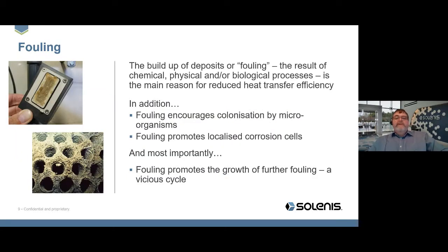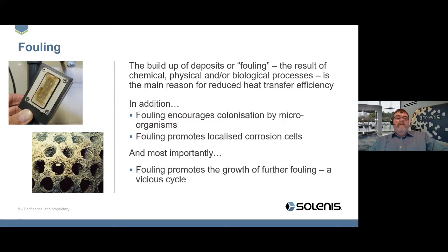Fouling is the buildup of deposits resulting from chemical, physical, or biological processes — it's the number one reason for reduced heat transfer efficiency. In addition, fouling encourages colonization by microorganisms, and it promotes localized corrosion cells, under-deposit corrosion, and localized attack. Most importantly, fouling promotes the growth of further fouling — it's a vicious cycle. Where we see fouling, we see continued fouling growth, microbial colonization, and considerably increased corrosion potential.